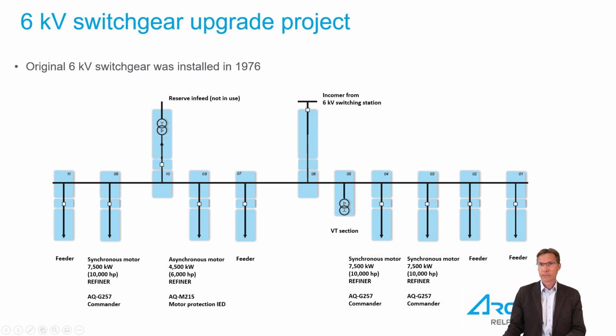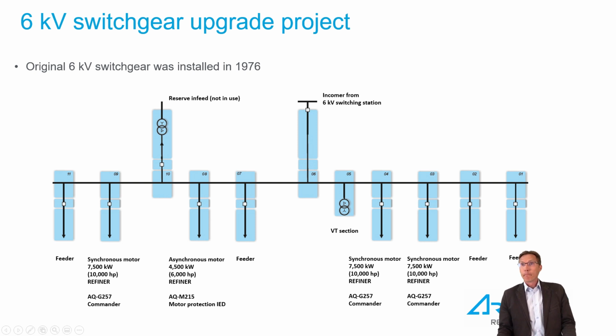The VT section actually became very useful and important in this part, since that was selected to be the final location for the arc quencher installed in the gear. Since these large motors were starting with the reactor in place, the voltage drop was quite considerable, and that was beyond acceptable limits, which again led to the need for removing the reactor from the system. And once this retrofit project was initiated, a total evaluation of the system was then done.